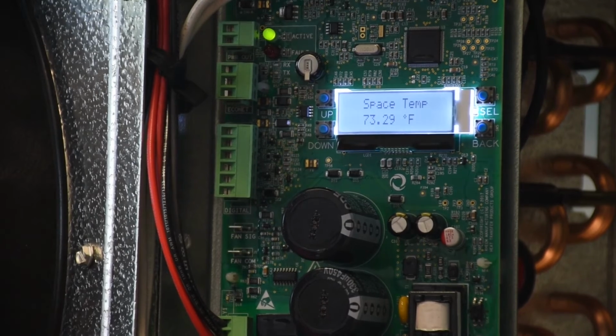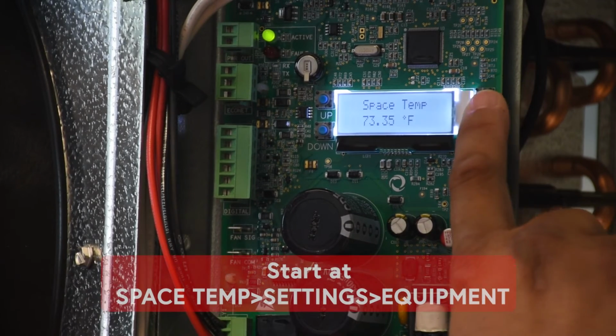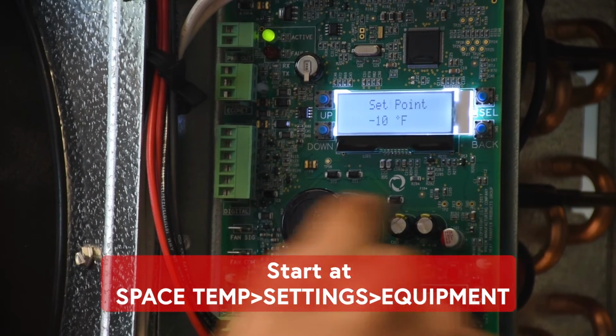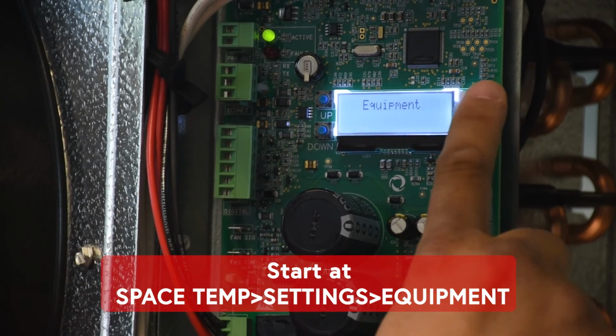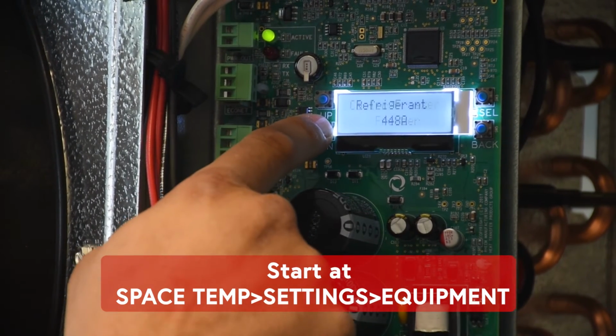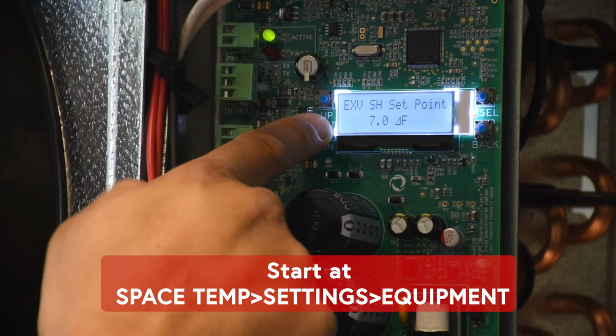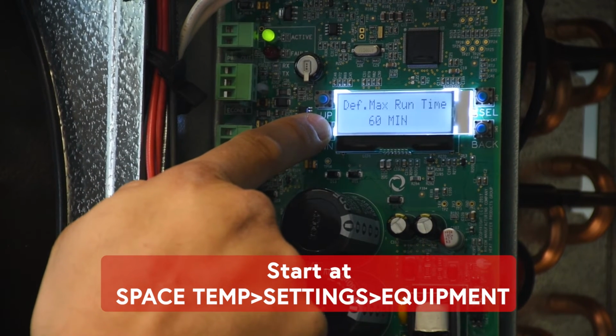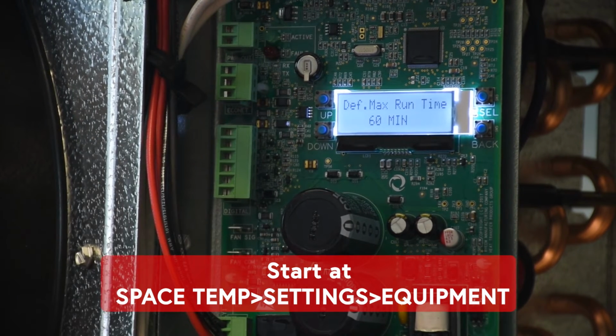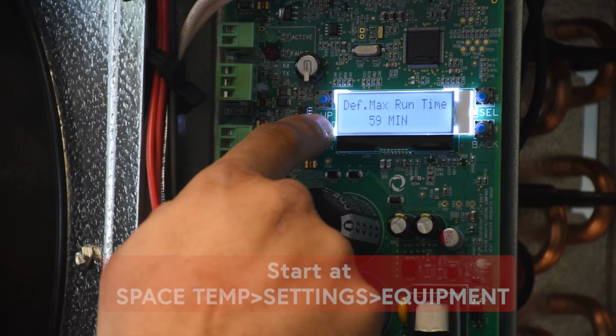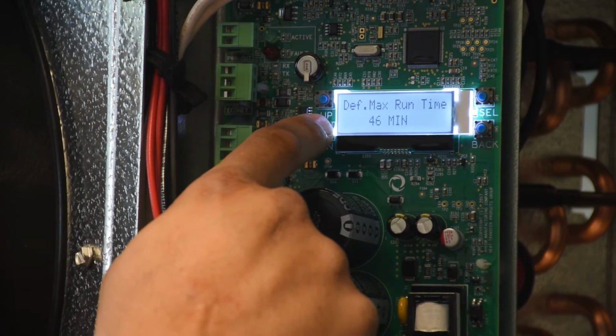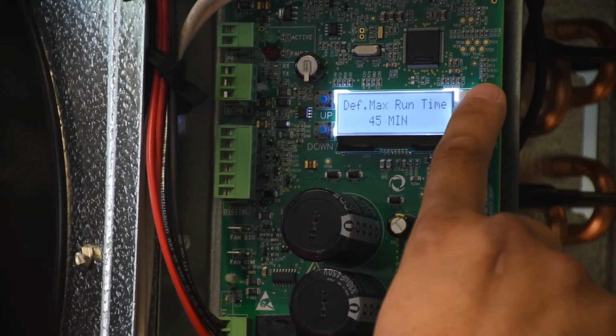To change the maximum defrost time on the controller, again, we will go to our settings, scroll down to equipment, and then look for the max defrost time setting. It's default 1 hour, but again, we can adjust it. And then hit select again to confirm the change.